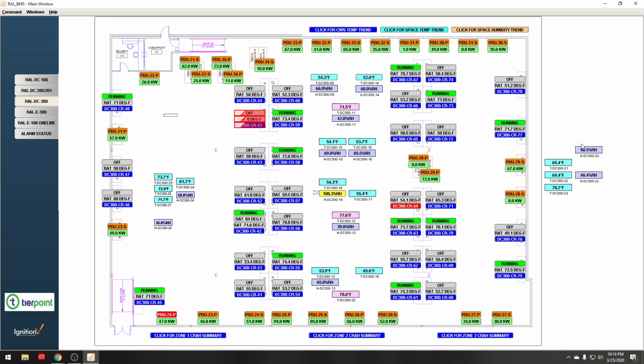This space has temperature sensors in it. So anything that's blue, we're monitoring the underfloor temperature. So that's the air leaving the floor into the server intake, which is very low right now. We are in process of fixing all of that. These are above floor right now as well. So these are kind of the ones that we've messed with, and it's working beautifully.